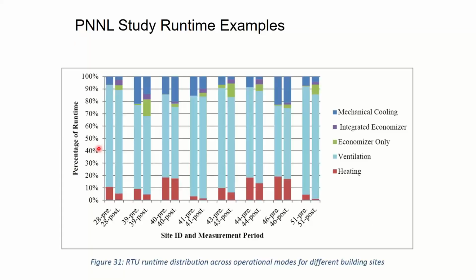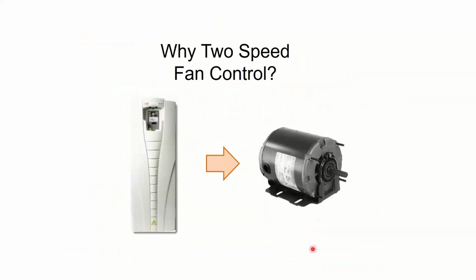So that basically means when we're in this red bar down here, we're at maximum speed. And let's just say for argument's sake, half of the dark blue bar, we're at maximum speed. Everything else is at the lower speed. We typically use VFDs to do that. The VFD is actually almost the same one that's in the picture, coincidentally.